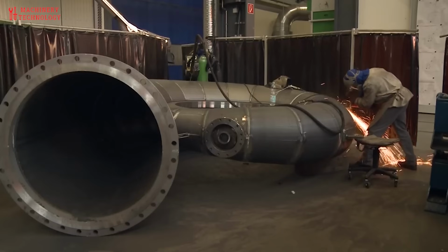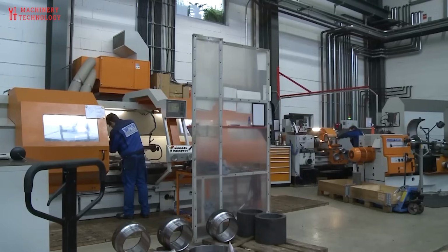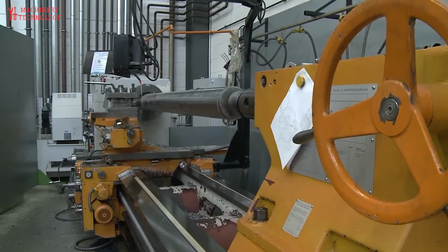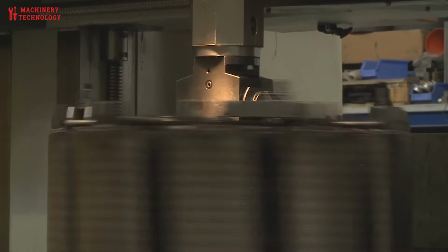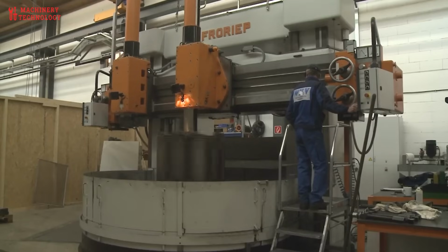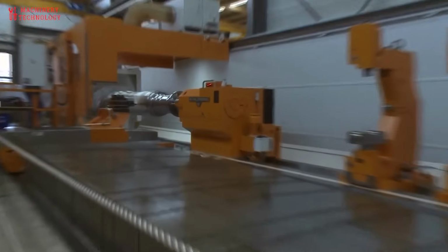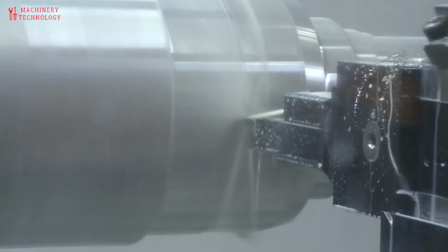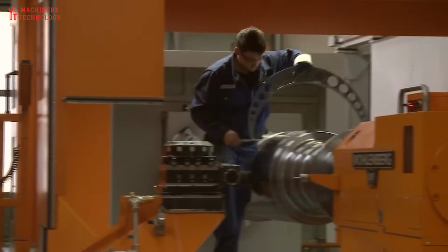Water turbines are generally divided into two categories: impulse turbine, used for high heads of water and low flow rates, and reaction turbines, normally employed for heads below about 450 meters and moderate or high flow rates. These two classes include the main types in common use, namely the Pelton impulse turbine and the reaction turbines of the Francis, Propeller, Kaplan, and Deriaz variety. Turbines can be arranged with either horizontal or more commonly vertical shafts. Wide design variations are possible with each type to meet the specific local hydraulic conditions. Today, most hydraulic turbines are used for generating electricity in hydroelectric installations.